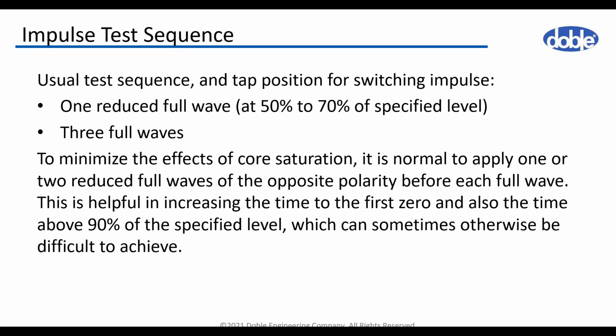The test sequence for switching impulse test consists of one reduced wave followed by 3 full test voltage waves. To minimize the effect of core saturation, usual practice is to apply impulses with reduced voltage and opposite polarity in between the test shots.